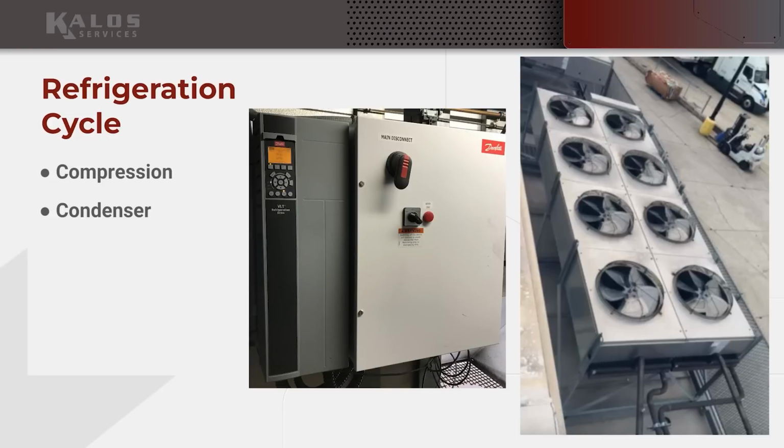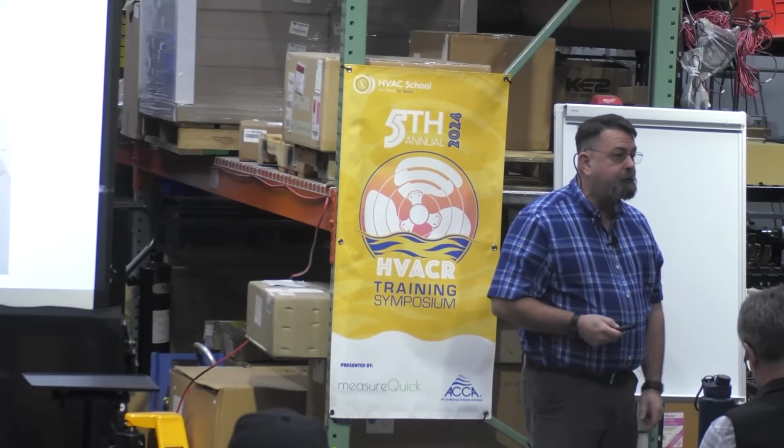All right, well, there it is. This shot of the condenser is from a rooftop looking down on that same rack I took a picture of earlier. You'll see the 50% splits right there, right? You can tell this condenser is actually 2 condensers split right down that line. That makes it a little clearer, okay?